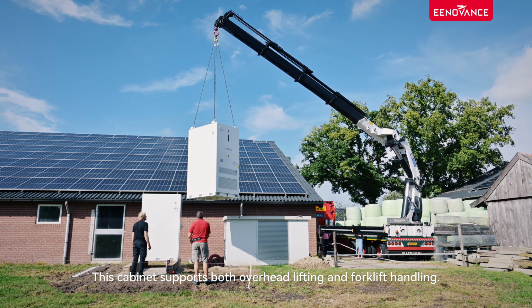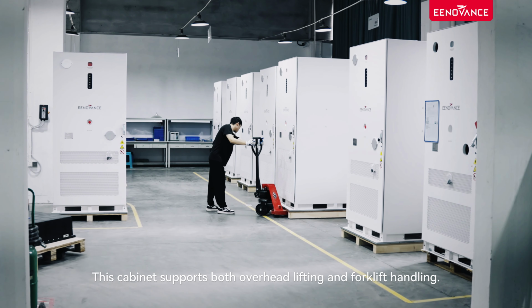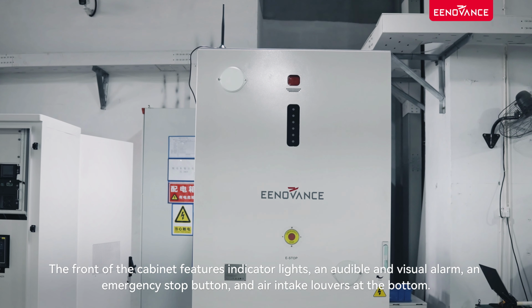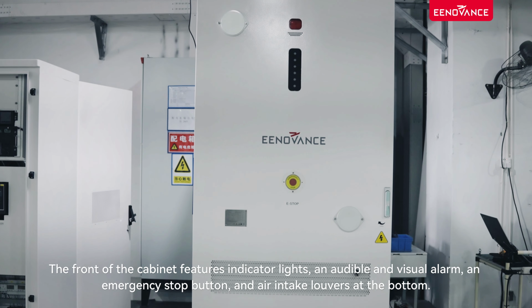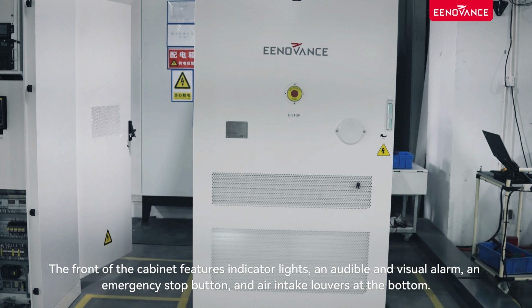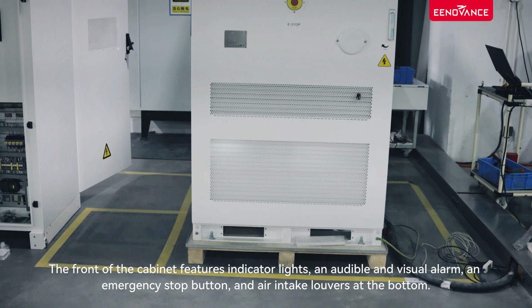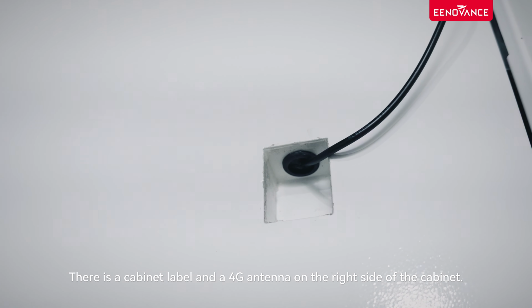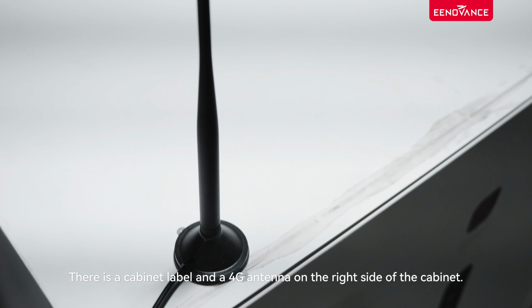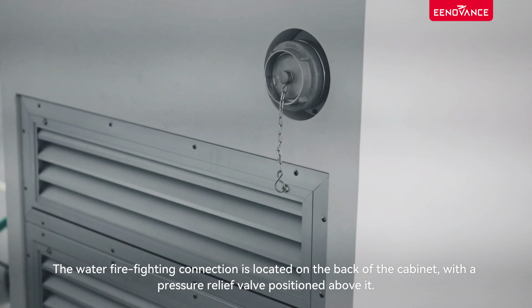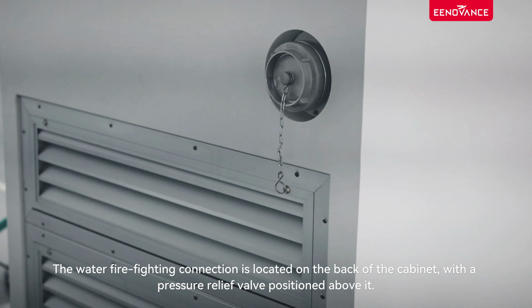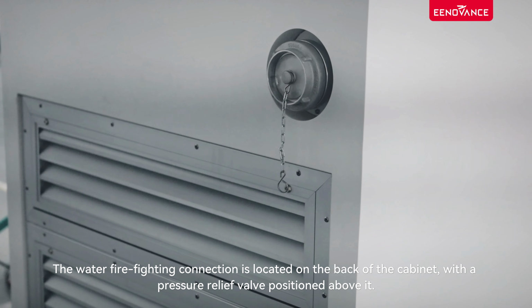This cabinet supports both overhead lifting and forklift handling. The front of the cabinet features indicator lights, an audible and visual alarm, an emergency stop button, and air intake louvers at the bottom. There is a cabinet label and a 4G antenna on the right side of the cabinet. The water firefighting connection is located on the back of the cabinet, with a pressure relief valve positioned above it.